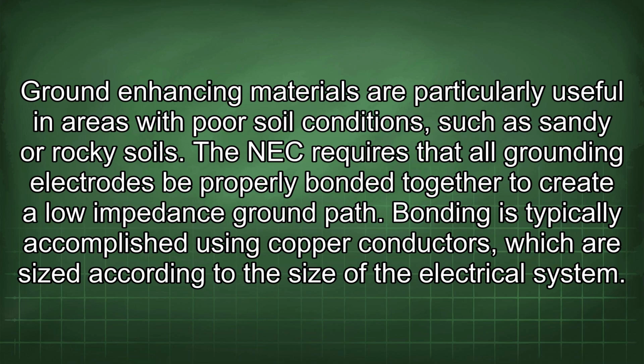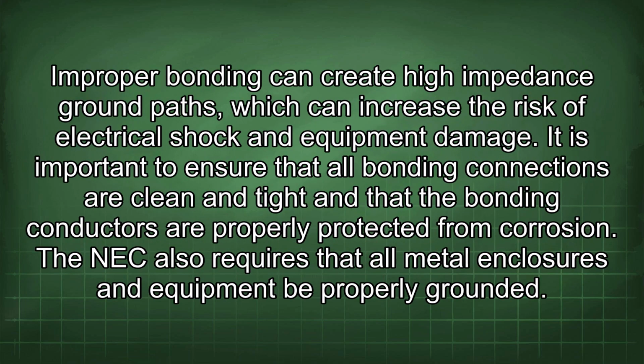The NEC requires that all grounding electrodes be properly bonded together to create a low-impedance ground path. Bonding is typically accomplished using copper conductors, which are sized according to the size of the electrical system. Improper bonding can create high-impedance ground paths, which can increase the risk of electrical shock and equipment damage.